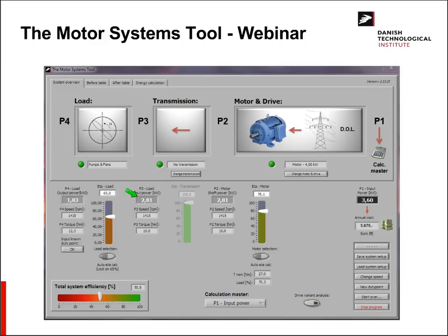For starters, the program just defaults with an automated ETA calc. It's right now locked on 65%, and that's just the default value. It comes from absolutely no real life thing. It's just a number to get us started. But in this example, I have actually been out measuring on the fan. That means that I can actually push this button down here. I have a known duty point.